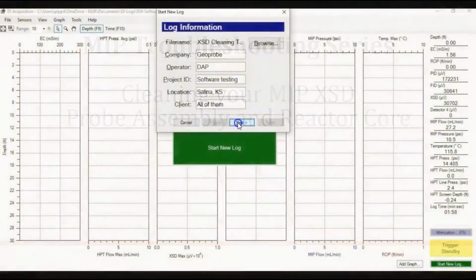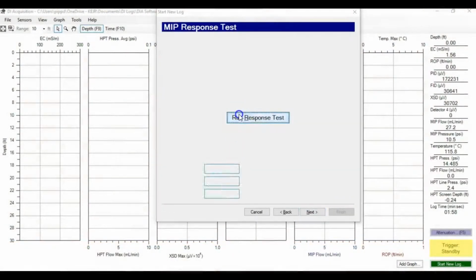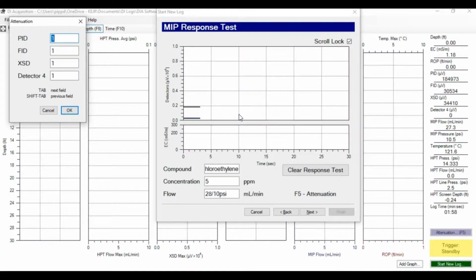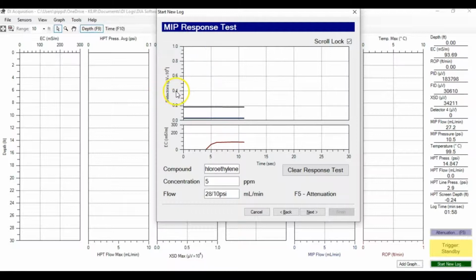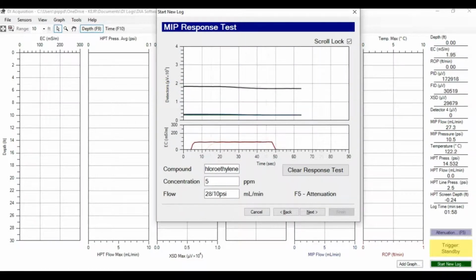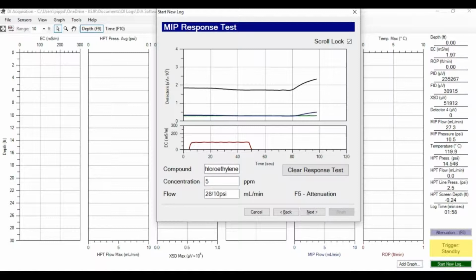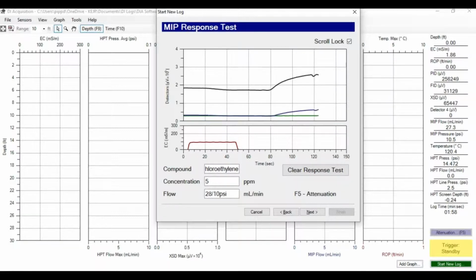The first step of this process is to run a chemical response test, here using 5 ppm of TCE. This will provide us with a baseline response of the PID and XSD detectors, which will help us to determine the consistency of the response to standard, as well as how well the cleaning has helped the XSD performance. Here, the top black line is the PID response, and the lower blue line is the XSD. Once we have this data, we can allow the detectors to cool and get on with the cleaning.